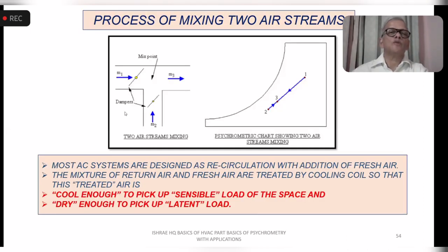This is again the repetition of the mixing. Most of the AC systems are designed with this recirculation, mixing, and the cooling coil treating it. So I am repeating the statement. The supply air has to be cool enough to pick up the sensible load. That means the dry bulb temperature of the supply air has to be low enough that once it picks up the sensible load of the space, the resultant temperature is within the acceptable range, or ideally the design parameter.